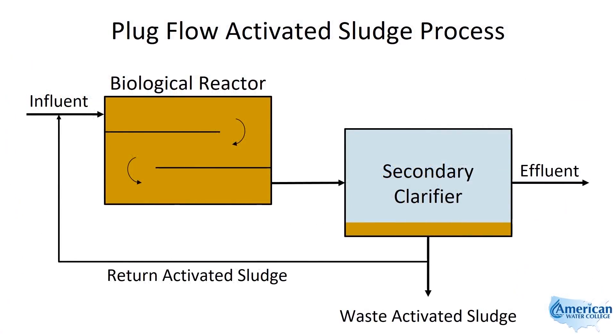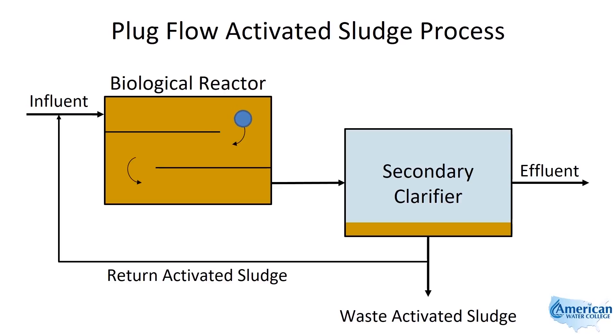The first configuration we'll look at is the plug flow activated sludge process. Flow enters one end and leaves at the opposite end, moving uniformly through the basin. The BOD concentration and the DO uptake rate will get smaller and smaller as the water moves through the basin. The total suspended solids and the volatile suspended solids will increase farther down the length of the basin as the bacteria grow and reproduce.